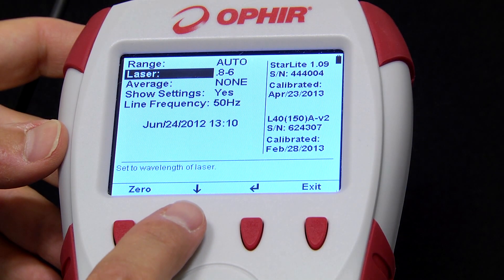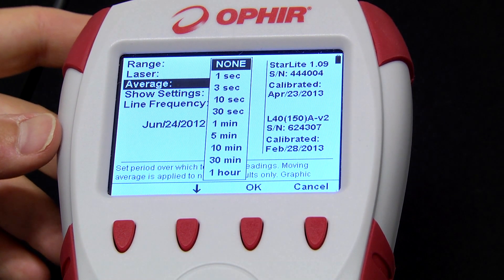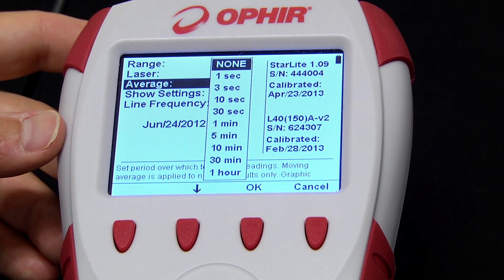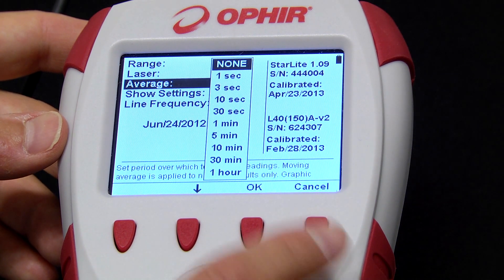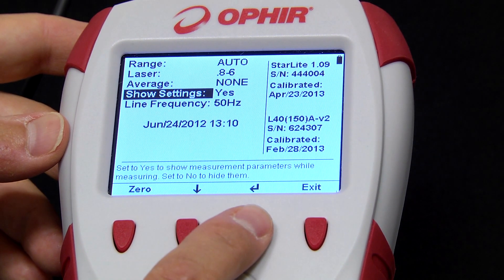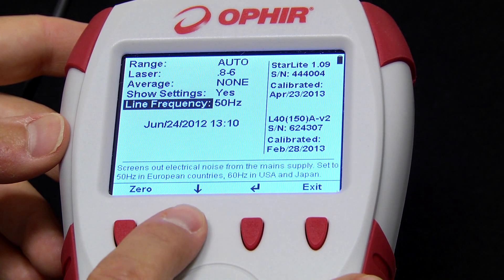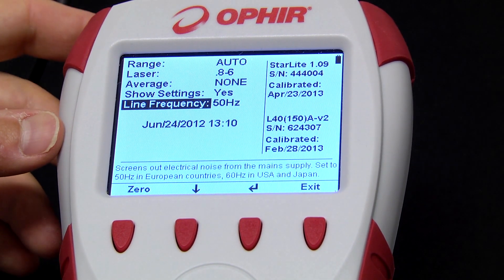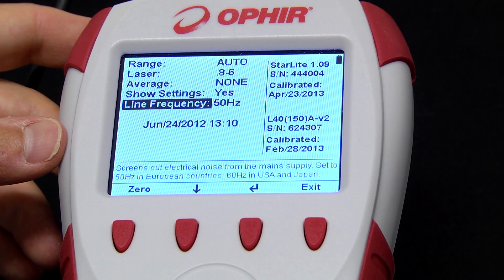We use Laser to select the wavelength. We can use the average function to display a running average over various time periods rather than the instantaneous real-time reading — we could use this to smooth out jumpy readings so they're easier to follow. Here we can set the StarLite to show or not show the settings on the main measurement screen. Here we set the AC line frequency depending on the country in which we're located so that any noise from it can be filtered out. Note the serial number and calibration date information shown on the right side of the screen.